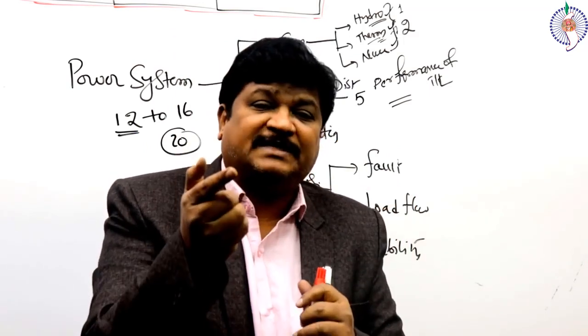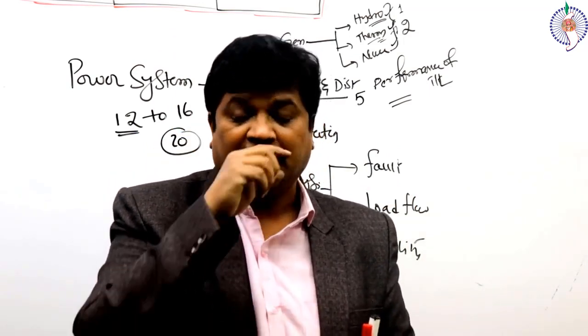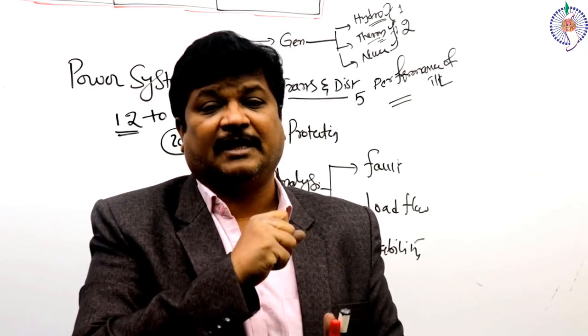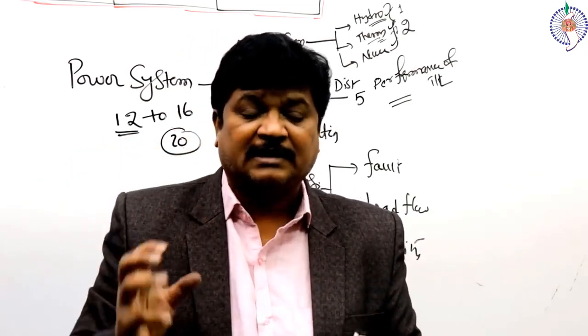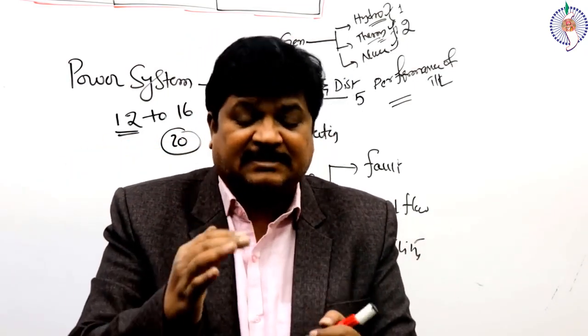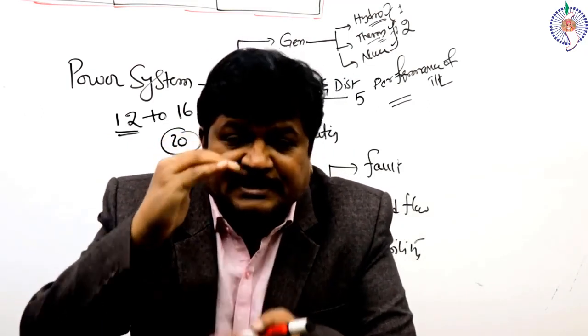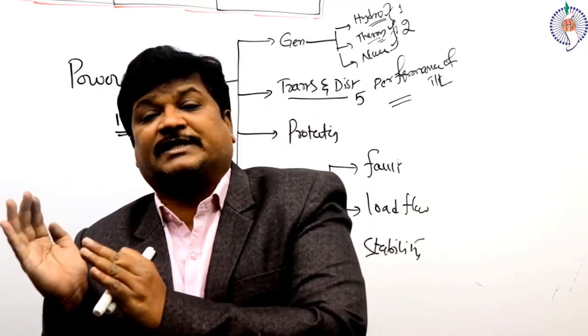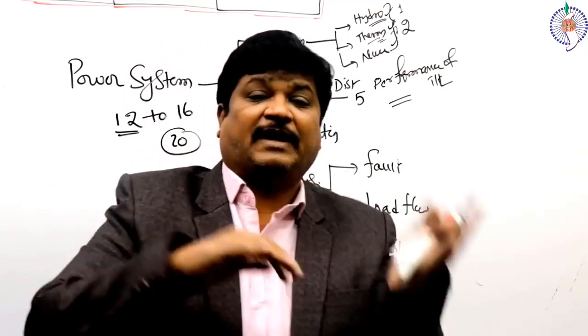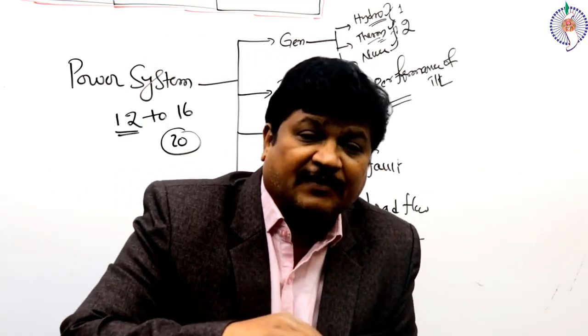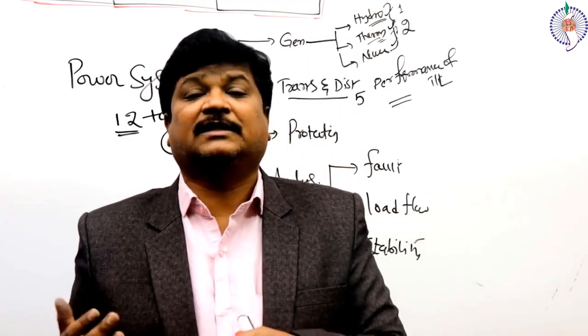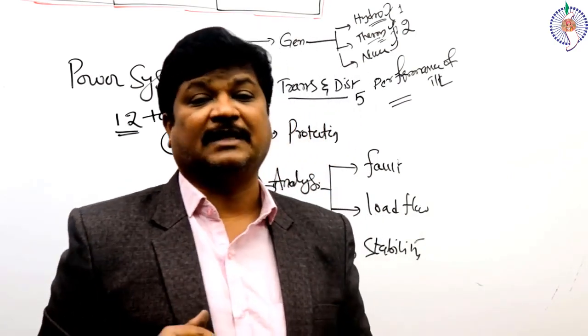And one more problem is there, which may require a calculator - in the case of an alternator, using differential relay, suppose a phase to ground fault occurs, how much winding is protected, how much winding is not protected, what is the percentage of winding protected versus not protected - that question, in rare cases, you may get.